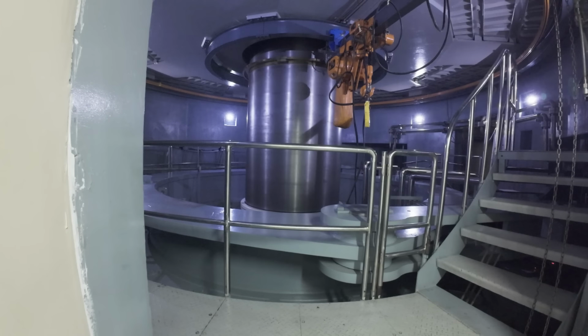As the rotor accelerates towards the rated speed, the entire powerhouse starts changing character. You begin hearing deeper mechanical resonance, and vibration increases. Massive rotating components come alive. The machine transitions from silence into controlled power, and remember, the PRV system is still standing by. Because if anything trips during acceleration, it immediately becomes the most important protection system in the plant.